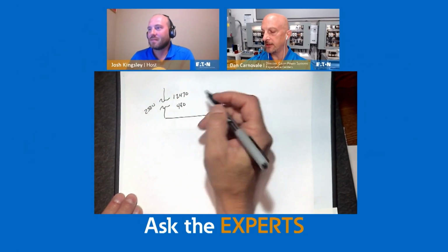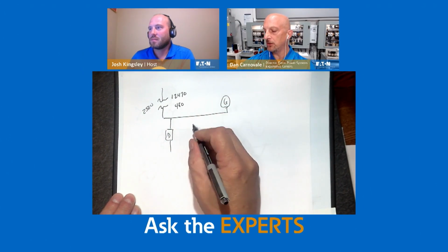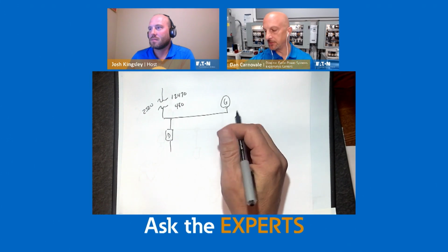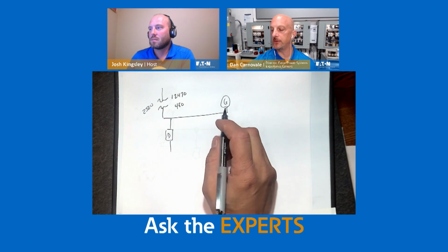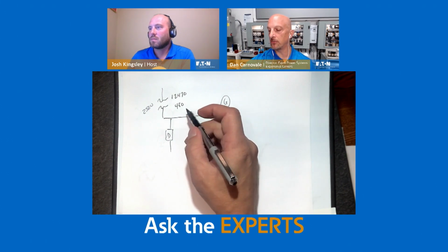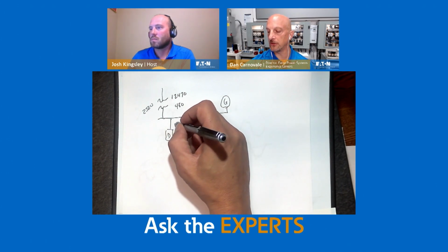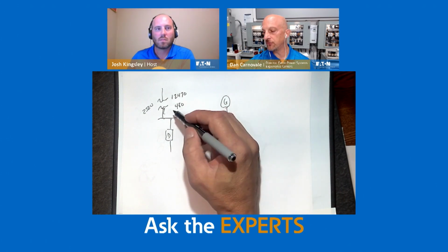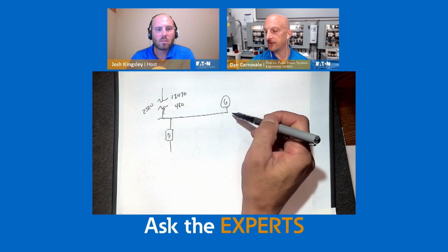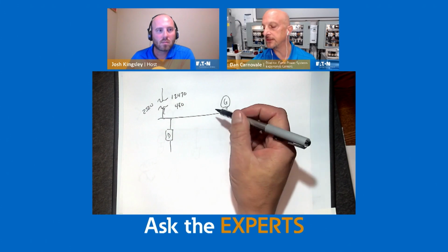I think so. So 12.47, 2,500 kVA, lots of harmonics. Everything on here is on drives, so they're running everything, and he says the harmonics disappear when they go on generator. I don't know if he means specifically, and maybe you could have a follow-up question, but the current, again, has to flow somewhere. The current's going to typically flow out and back on the transformer out to all the different drives. So if we transfer to the generator, we would have the same thing. If the generator's running in parallel, likely a lot of the harmonics will still go back to the utility, as that's a lower impedance in terms of current.